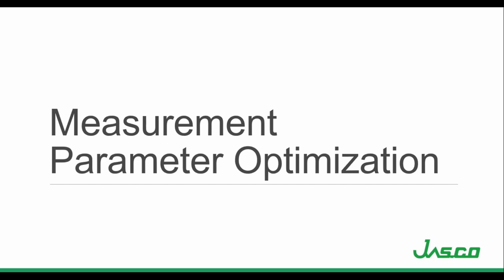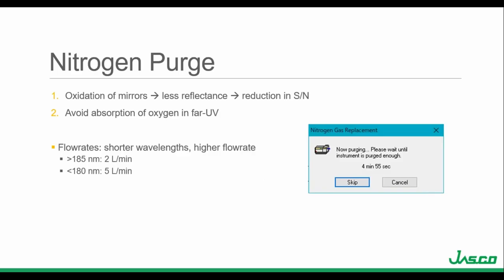Now I'm going to go into measurement parameter optimization — the parameters of the actual instrument. From our first CD webinar, I went over the importance of nitrogen purging for most CD measurements. To summarize: we want to purge the instrument monochromator of oxygen with nitrogen for two reasons. The lamp creates UV radiation, and when UV radiation interacts with oxygen, it creates ozone. Ozone oxidizes the mirrors in the instrument, causing them to lose reflectivity, which causes less light throughput through the monochromator, reducing the signal to noise of the spectrum.